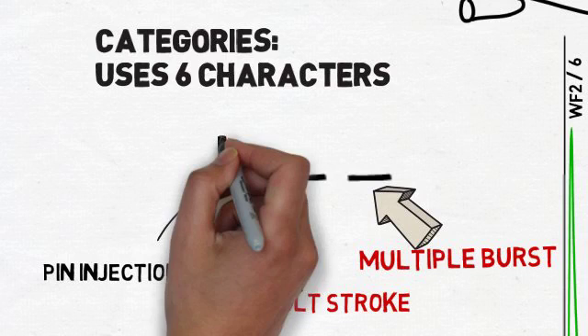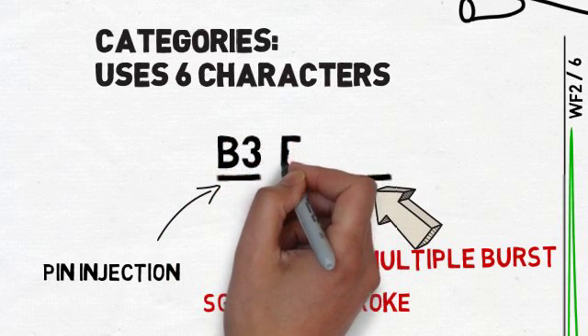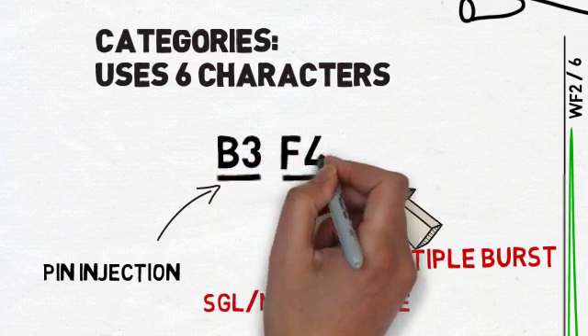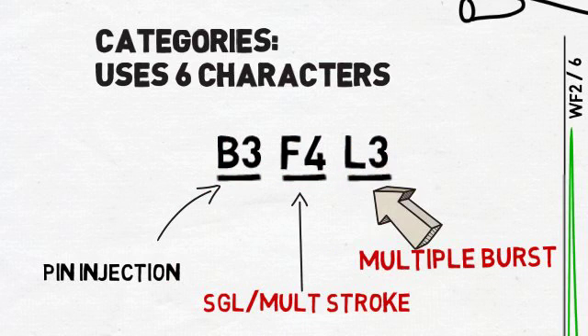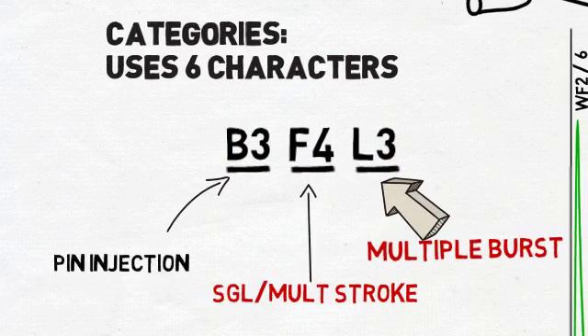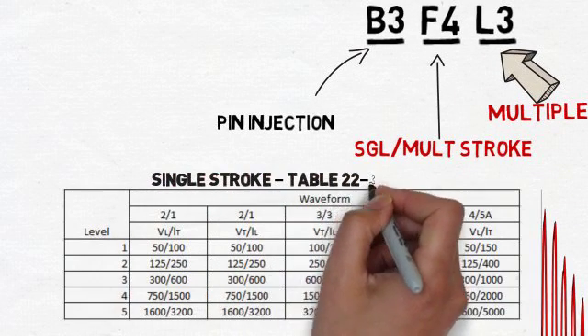In this example, we see that B3 is the waveform set and level. F4 is the single stroke and multiple stroke waveform set and level, with L3 being the multiple burst waveform set and level. Looking at waveform set F for single stroke and multiple stroke, we need to test to waveforms 3 and 5A.